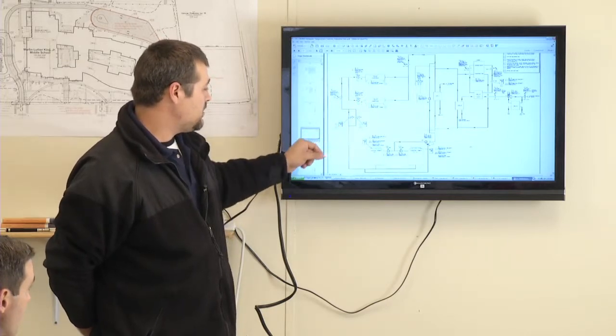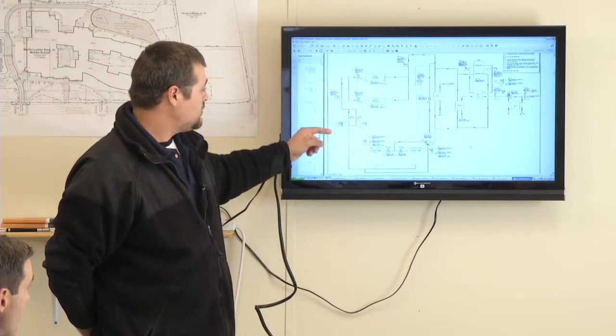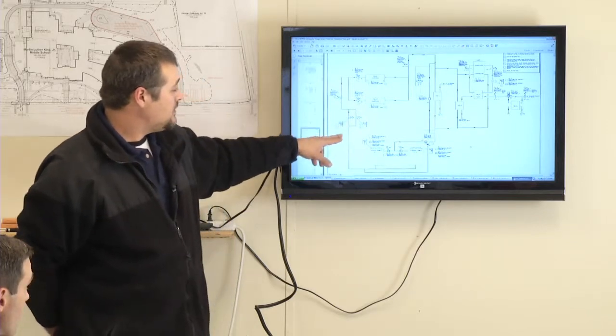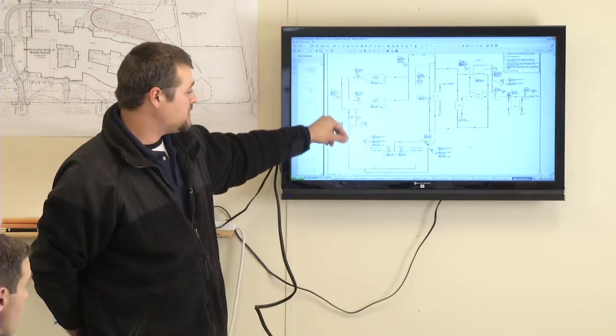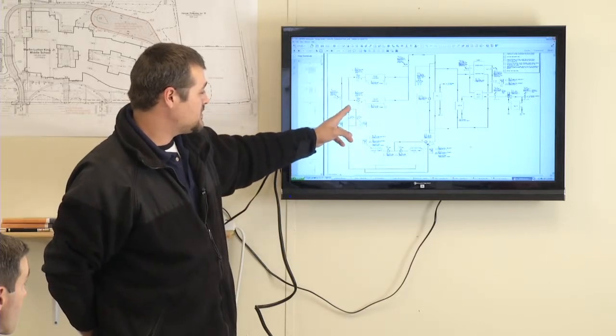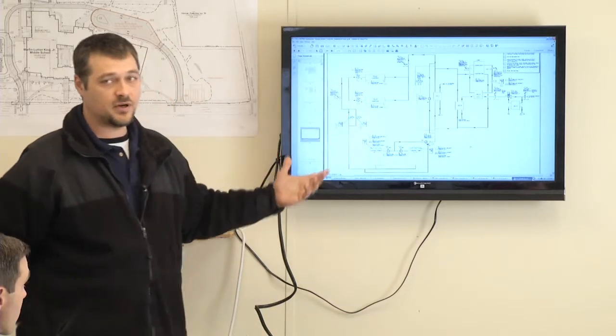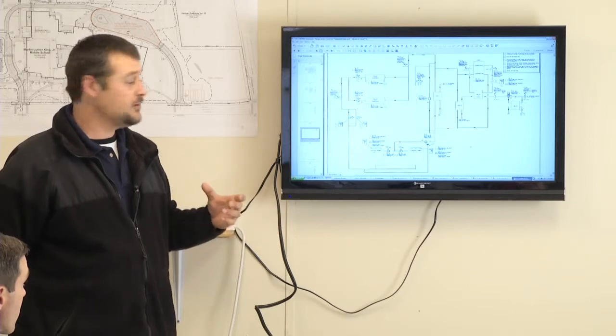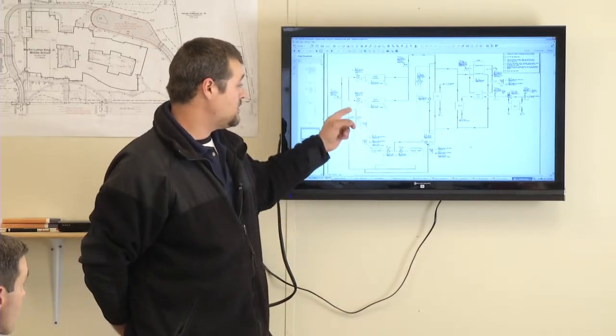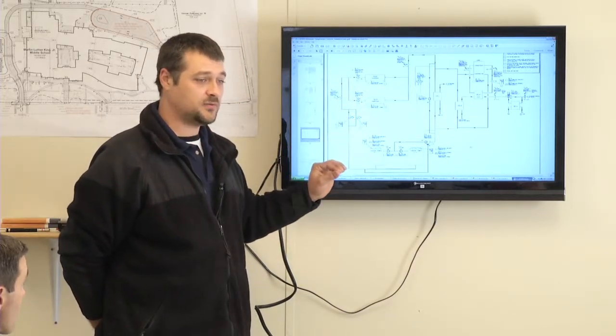So we have the water coming from the cooling tower, going through whichever pump is selected on the skid, pumping our condenser water, and this just illustrates the barrels of the condenser side of each chiller. Each chiller system has its own isolation valve, so we can manipulate flow through those. If chiller 1 is down, this valve will be closed. As you can see, each valve is also normally closed. It takes power to drive open, or there's a manual lever on the side of those valves where you can manipulate the position if necessary. They are 120 volt sourced, and then it takes a 24 volt actuation to make them move.